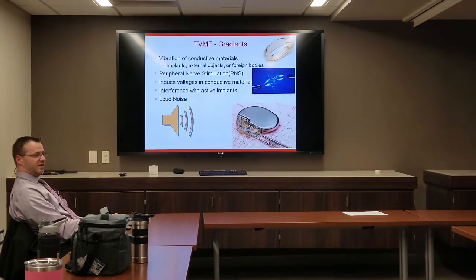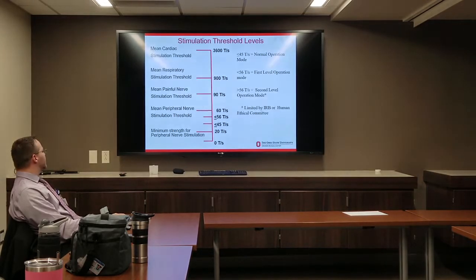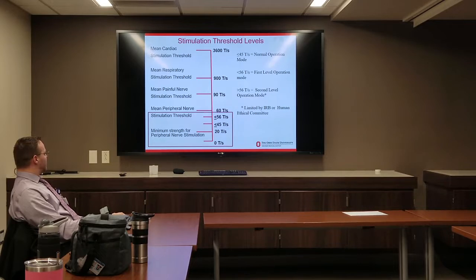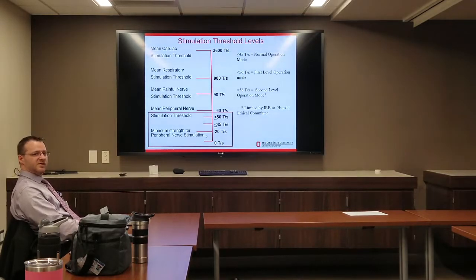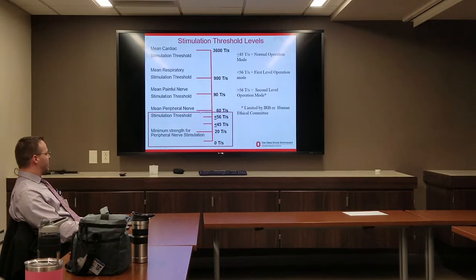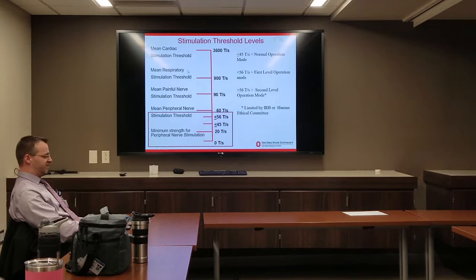The time-varying gradient field is also the source of the very loud noise in the scanner. For nerve stimulation, for the most part when operating an MRI clinically, most people don't experience nerve stimulation, though some sequences will cause it in some people. We aren't able to reach the area where nerve stimulation would cause pain within MRI at clinical operating levels.